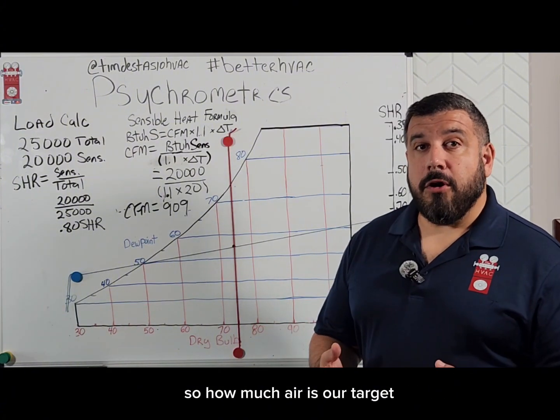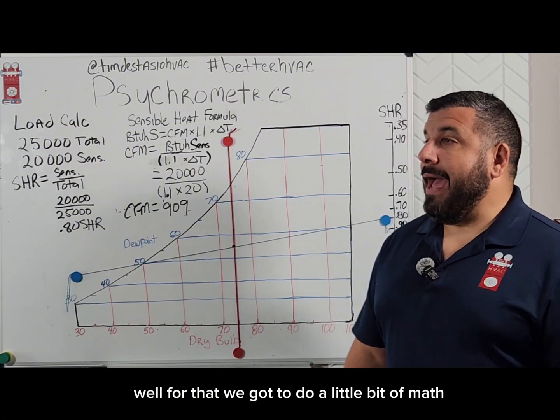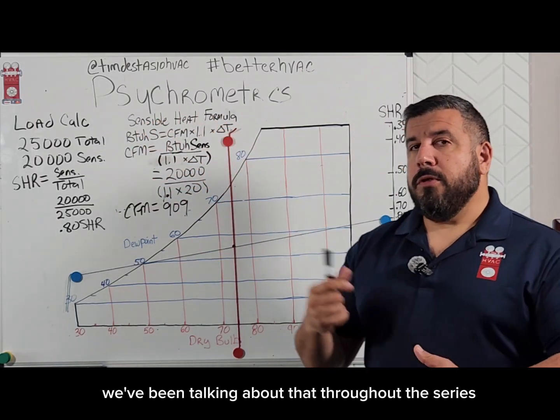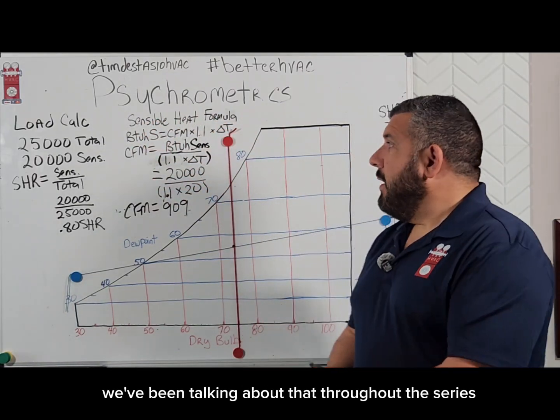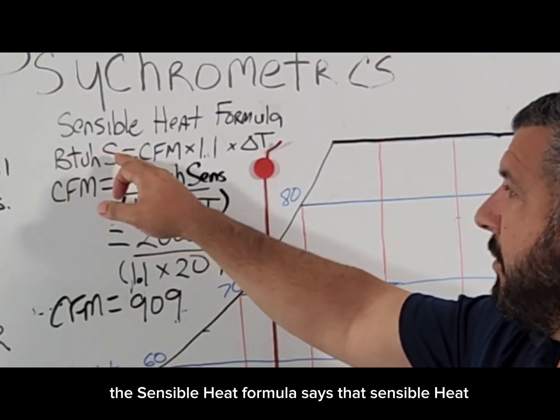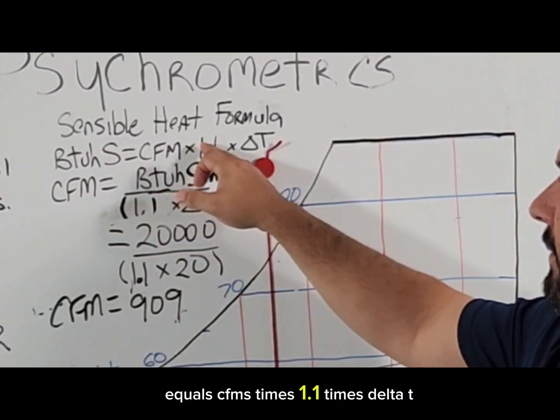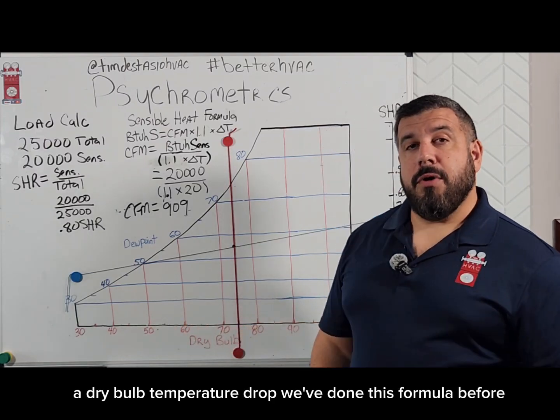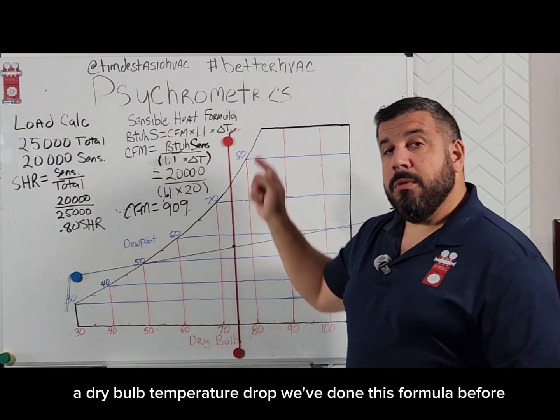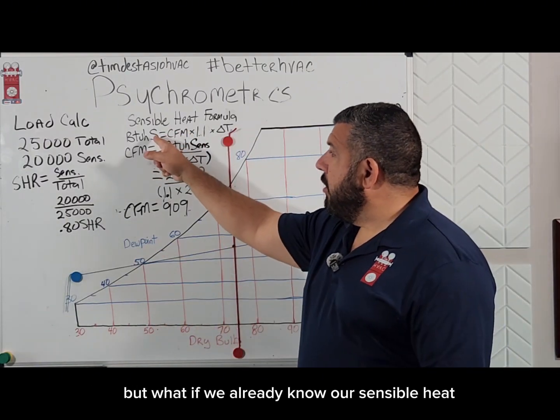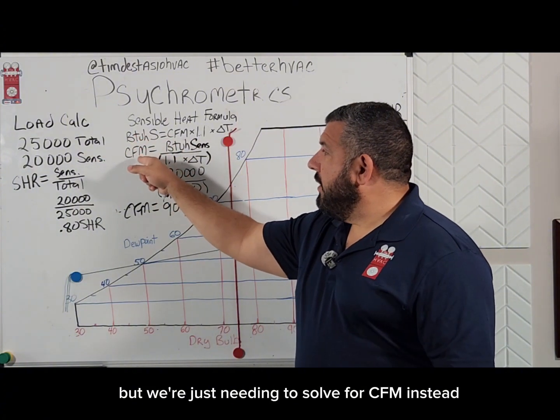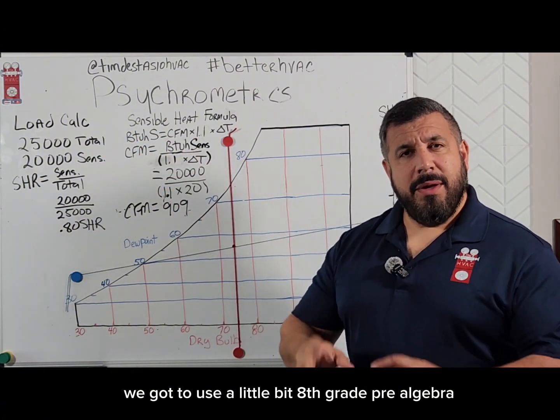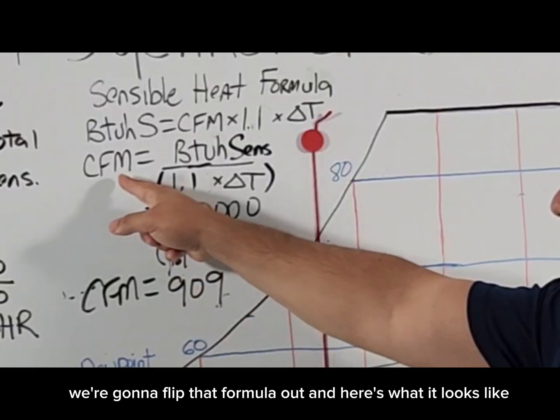So how much air is our target? We need to do a little math using the sensible heat formula we've discussed throughout this series. That formula says: sensible heat equals CFM times 1.1 times delta T (dry bulb temperature drop). But if we already know our sensible heat and need to solve for CFM instead, we use a little pre-algebra and flip the formula around.